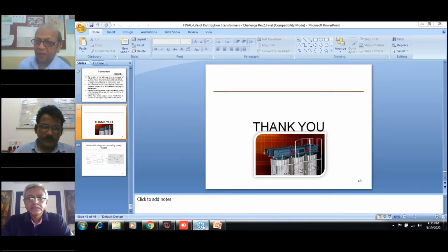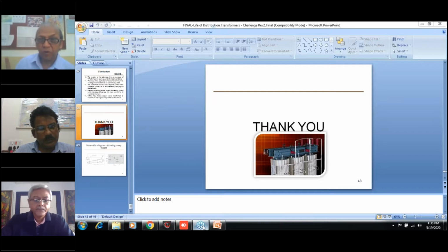Our transformers, in our conditions, are subjected to many adverse factors: switching, overloading, and temperature variations. This is causing a lot of cost to us, so it has to be looked into from that perspective. As I mentioned in my lecture, transformers should not be switched off on no load. Whenever you switch off a transformer, there must be some load, just like when switching off a motor.